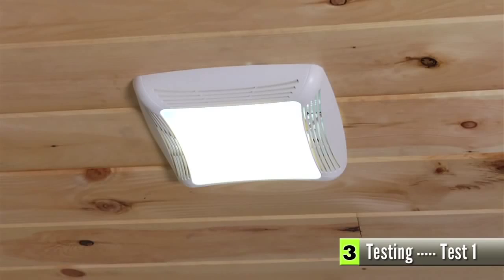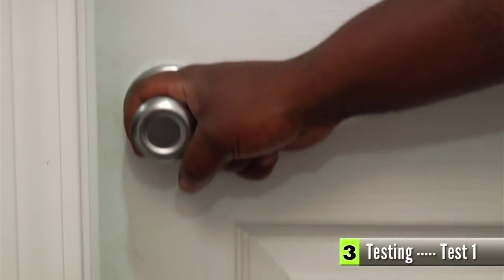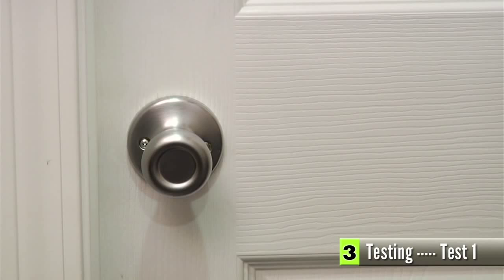You'll have to experiment with different scenarios in order to find the most negative CAZ pressure, so just remember those 4 steps. First, turn on the exhaust fans. Second, manipulate the doors, open and close. Third, turn on the air handler fan. And fourth, open and close the doors again. Whichever one of those 4 scenarios gives you the most negative pressure, record that pressure.